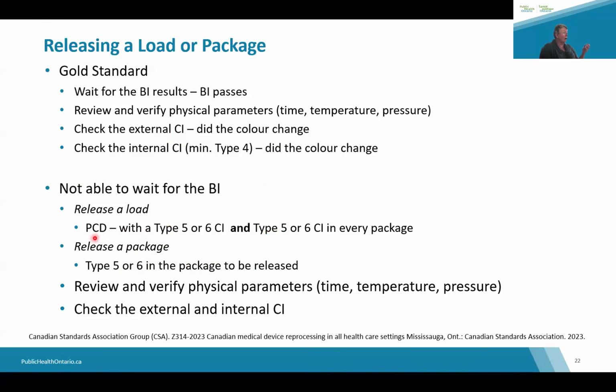So you could run a type 5 or 6 in a PCD and then have a type 5 or 6 in every package, and review and verify the physical parameters, time, temperature, and pressure, and check that your chemical indicators on your packages have passed. That's how you could release a load.